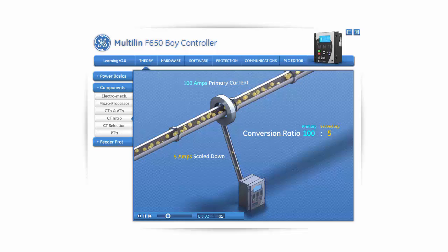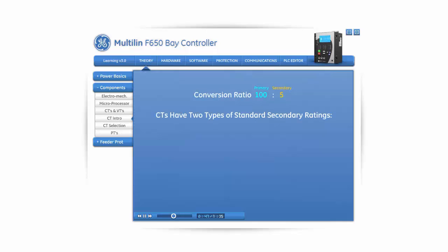The 5 amp measure is known as the secondary nominal current. If a fault were to occur on this phase that increases the primary current to 200 amps, then 10 amps would be passed to the relay through the secondary windings, consistent with the ratio. CTs have two main secondary ratings, 5 amps and 1 amp, while primary ratings are available at various different levels, for example 100, 150, 200, etc.